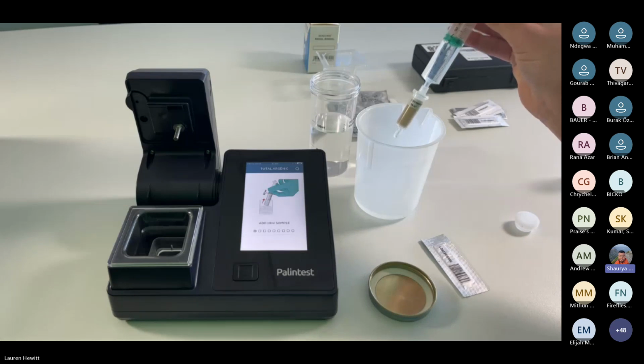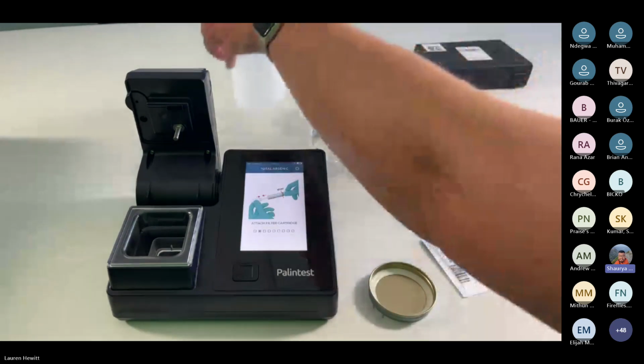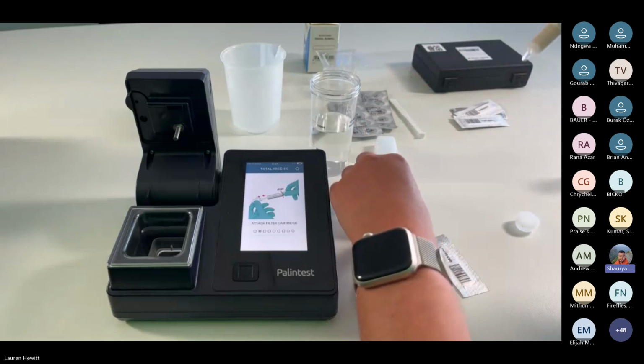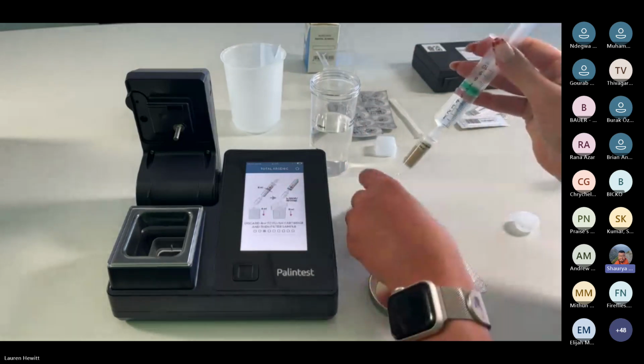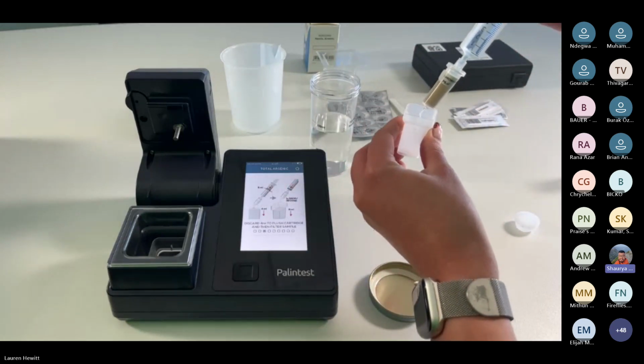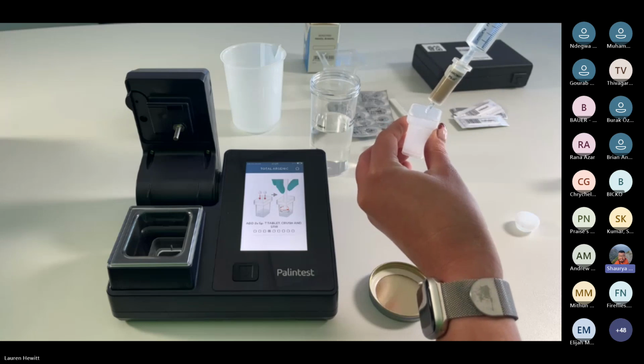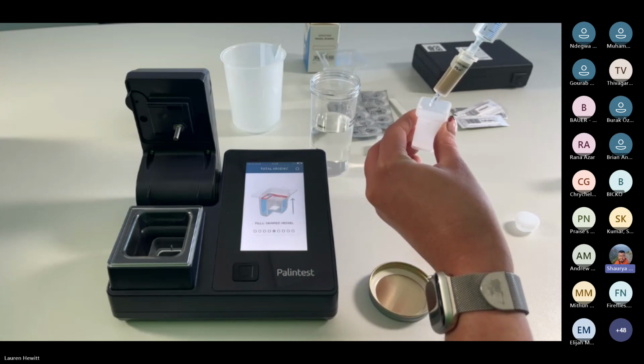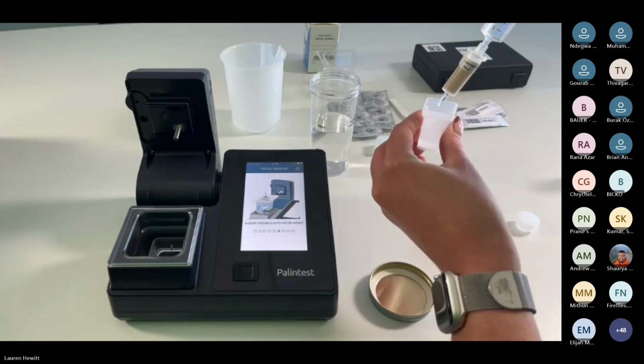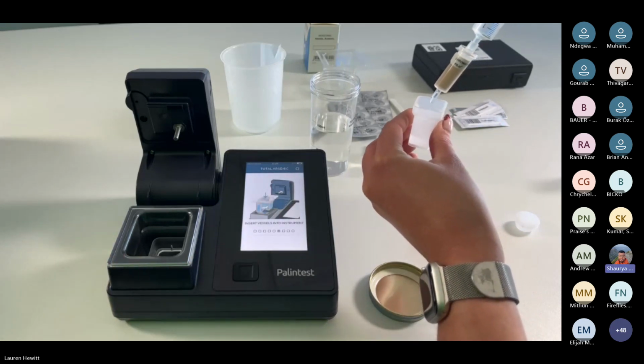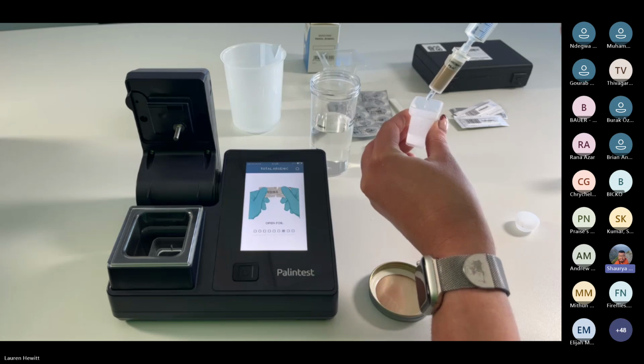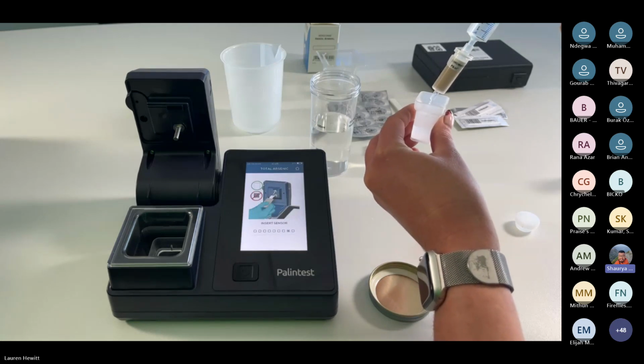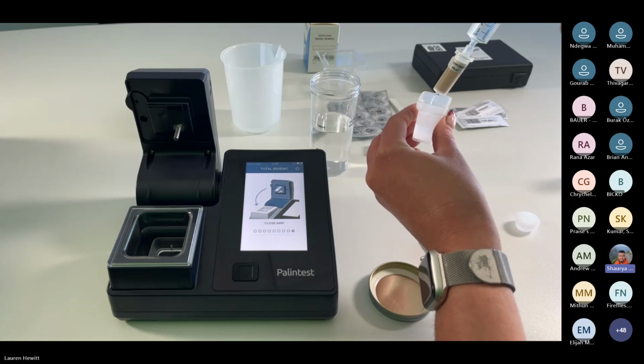Again, this is really important because it has to be done at this speed to ensure that the metals in the sample have enough time to bond with the resin. So now you want to pass the remaining 6 ml into the sample pot. Passing this through again at a steady pace to give sufficient time for those metals to be removed, and you can ensure that anything that may interfere, any metals in there, are removed and you are getting an accurate arsenic result.